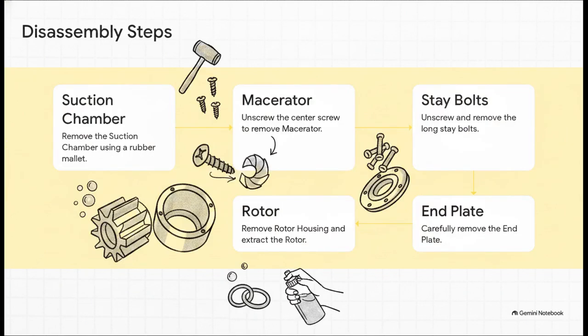Once everything is safe and upright, you've got a very strict sequence to follow. You're going to work your way inward from the suction side. First, remove the 4 screws to take off the suction chamber. You might need a rubber mallet to gently tap it loose. Then, unscrew the center screw to remove the macerator. Next, pull out those long studs. Only after that can you safely remove the end plate, the rotor housing, and finally extract the rotor itself. Oh, and a pro tip, straight from the manual, always use new O-rings and use a little soap water when you're seating those new shaft seals. It makes a huge difference.